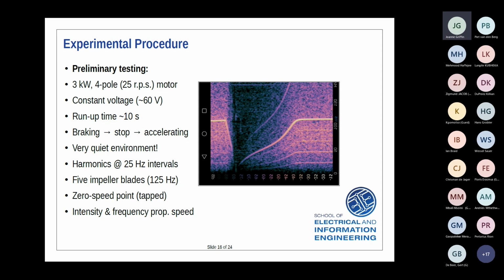Okay, just to show you something else, you can see where the machine stopped was quite problematic. There's almost no signal, no sound being produced by the machine. Obviously, it's not rotating anymore. And what I resorted to in the end was, you can see there's a very faint vertical line, basically the whole way up, is I could watch the machine. As the machine stopped, I could just tap my recording device with a pen and say, right, that's where it stopped. And you can see there, that's where I tapped. I tapped my phone, actually, the phone recorded an impulse when I tapped it. So I know that the zero speed point is down here. And you can sort of see that's where it converges. If you follow this line backwards, that's where it converges down there.